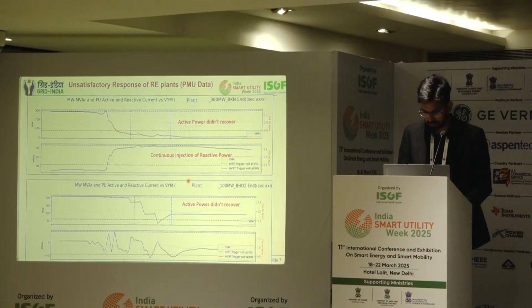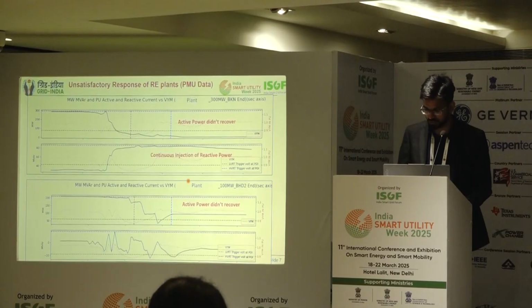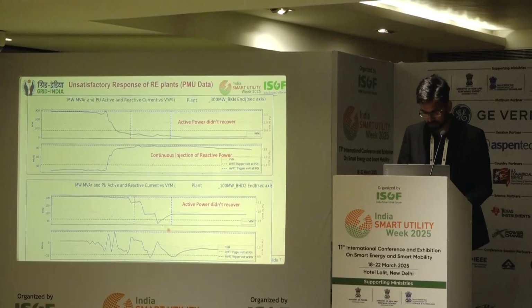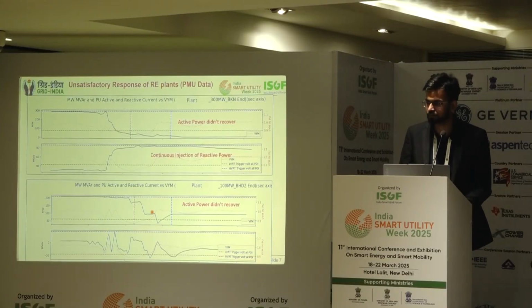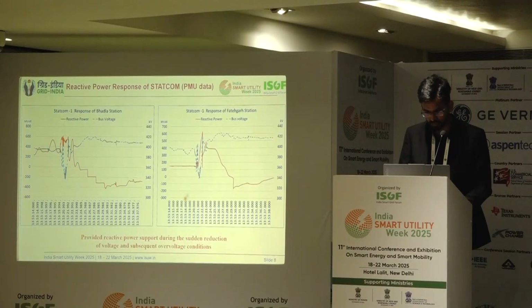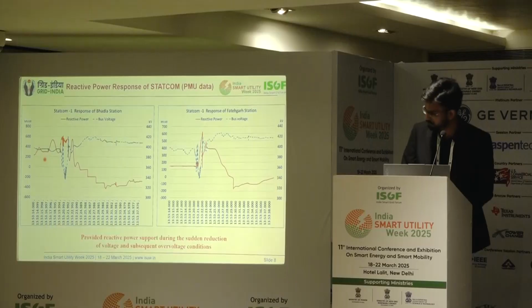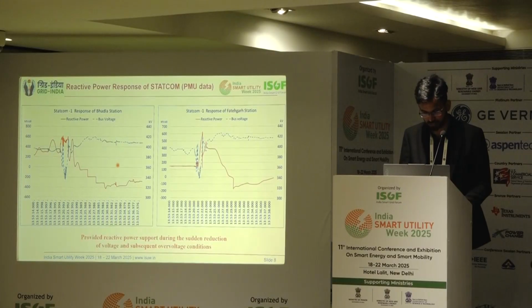Also, we studied a plant from a different pooling station, Bhadla 2, and in that plant we observed that the plant didn't trip, but it was not able to recover 90% of its pre-disturbance generation. Also, its reactive power injection into the system was not as per the standards. We also have STATCOMs in those regions. We observed that although the STATCOM helped us stabilize the voltage, due to the frequent faults in that area we were not able to utilize the whole dynamic reactive power of the STATCOM because it was already exhausted.